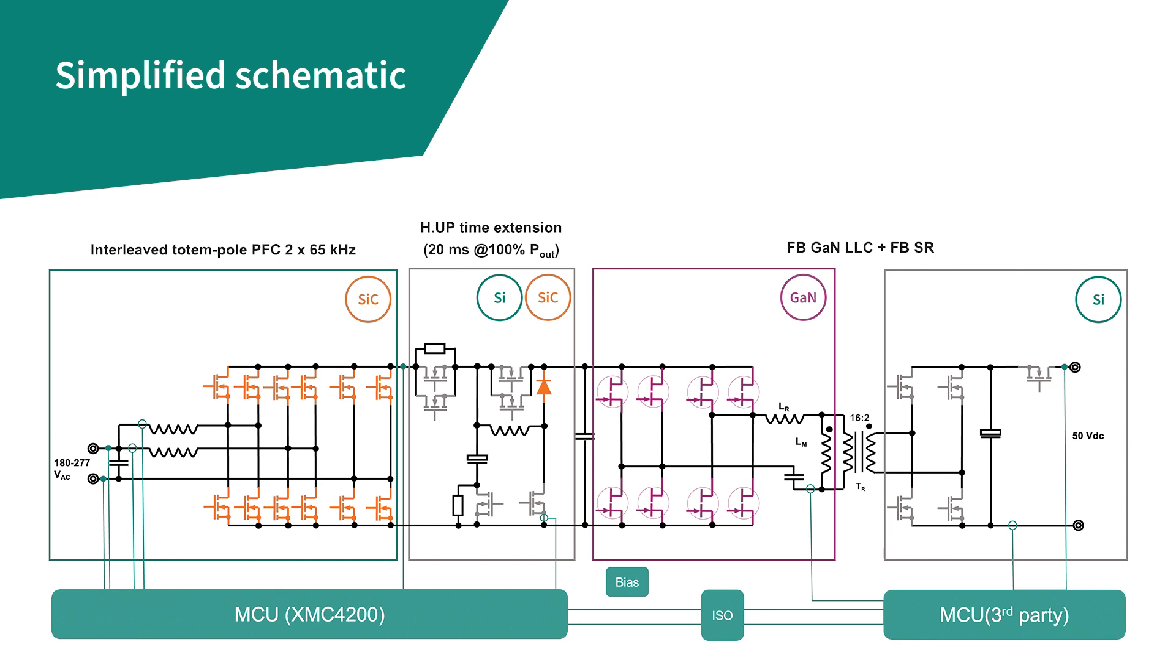An auxiliary power circuit for in-rush, re-rush, and hold-up time extension is connected between the first AC-DC PFC and the second DC-DC conversion stage. This stage enables 20 millisecond hold-up time and controls in-rush and re-rush currents during line cycle dropout events.